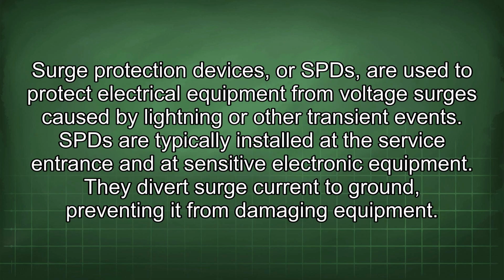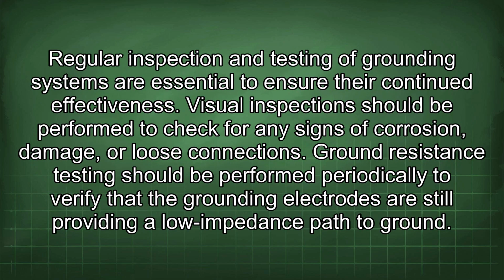Surge protection devices, or SPDs, are used to protect electrical equipment from voltage surges caused by lightning or other transient events. SPDs are typically installed at the service entrance and at sensitive electronic equipment. They divert surge current to ground, preventing it from damaging equipment. Regular inspection and testing of grounding systems are essential to ensure their continued effectiveness. Visual inspections should be performed to check for any signs of corrosion, damage, or loose connections.